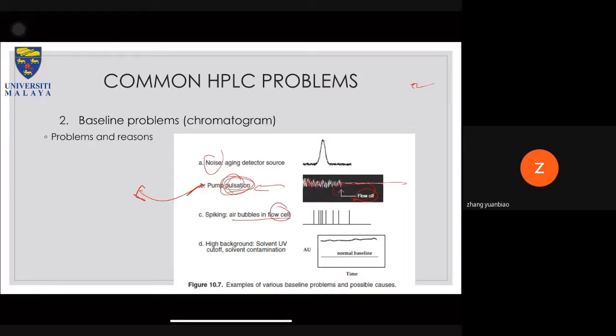Spiking in a chromatogram can be a result of an air bubble in a flow cell. The flow cell is inside the detector. Normally you have a flow cell like that, and you have your light source coming in, and your solvent is moving towards that direction. If you have an air bubble somewhere here, when the solvent pumps in, the air bubble might move in front of the light source, and therefore give you some reading.